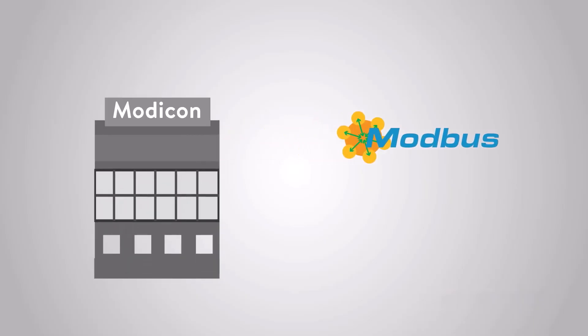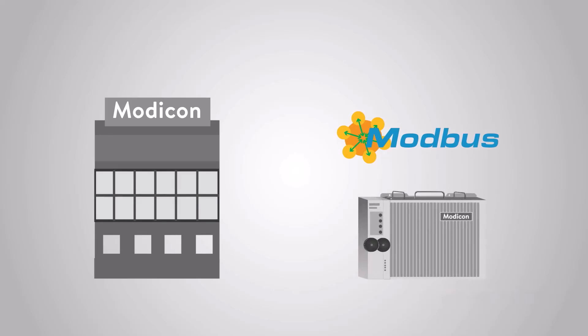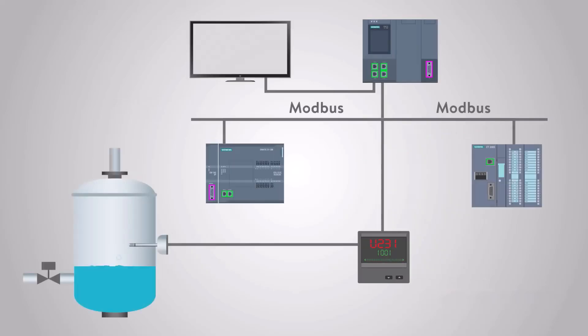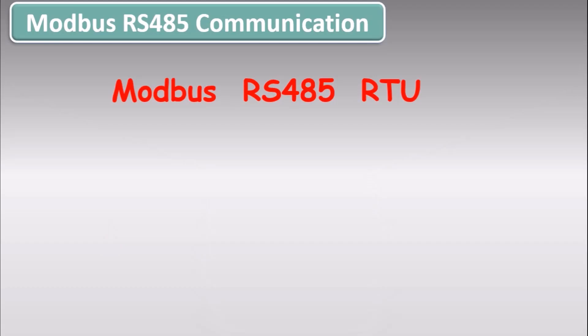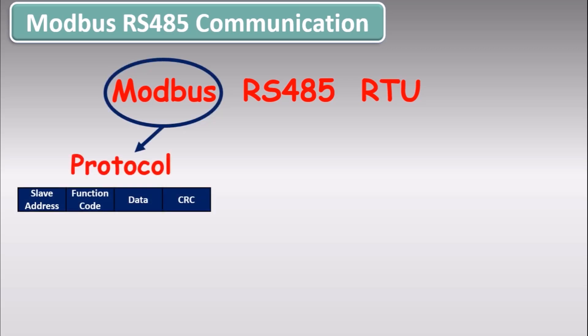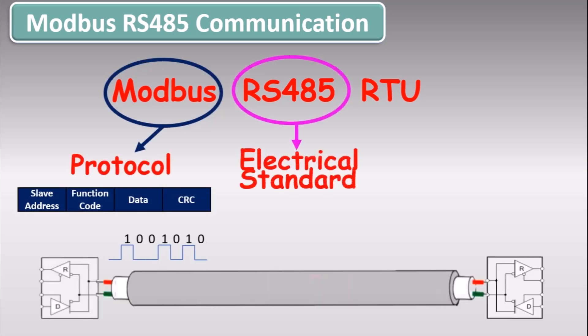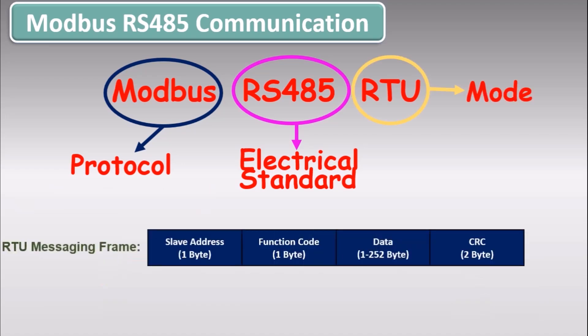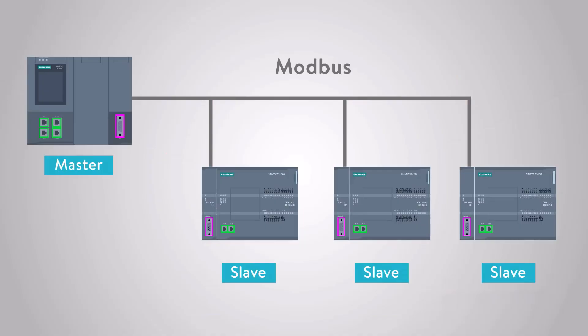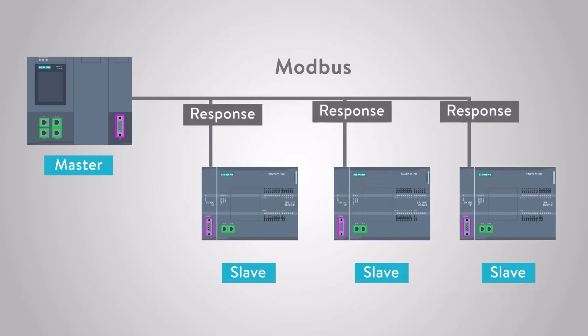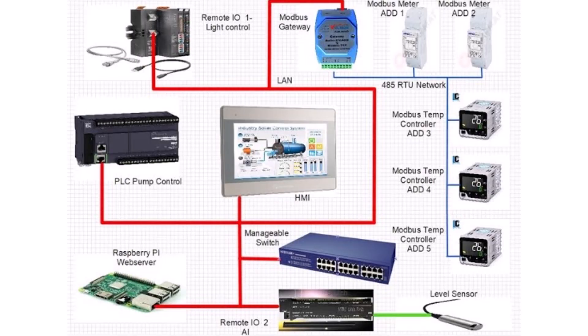Modbus is a communication protocol developed in 1979 for use with programmable logic controllers, also known as PLCs. It has become a de facto standard communication protocol in the industry and is now commonly used to connect industrial electronic devices. Modbus RTU, which stands for Remote Terminal Unit, is a variant of the Modbus protocol that uses binary coding and serial communication to achieve high-speed data transmission. It is widely used in industrial environments for connecting equipment such as sensors, instruments, and actuators to controllers and computers, mainly over RS485 serial interfaces.